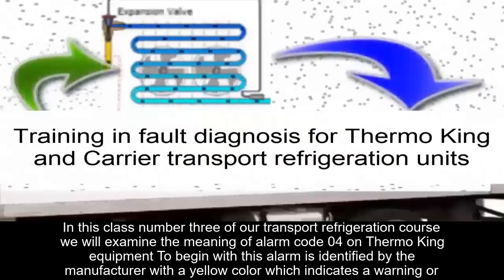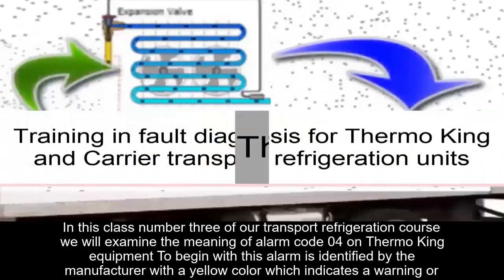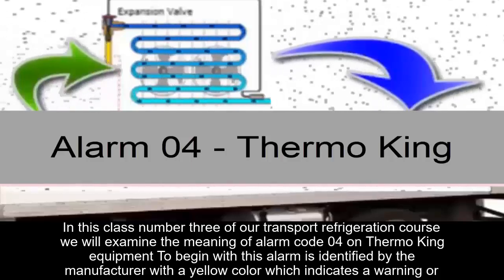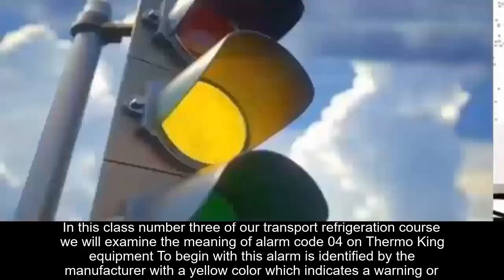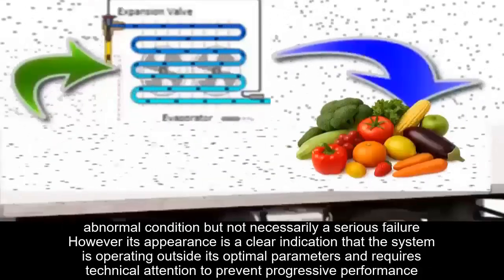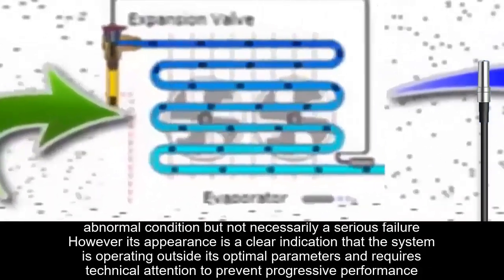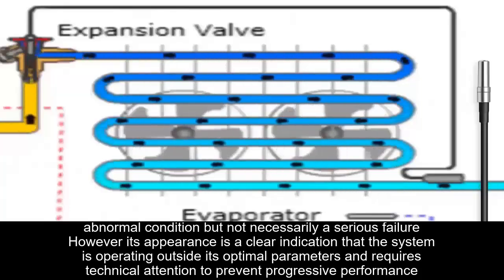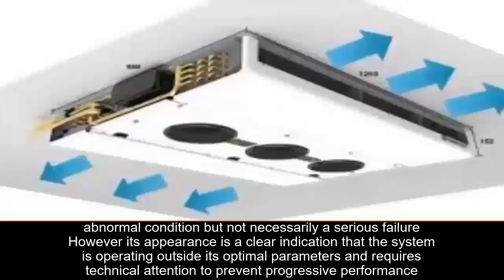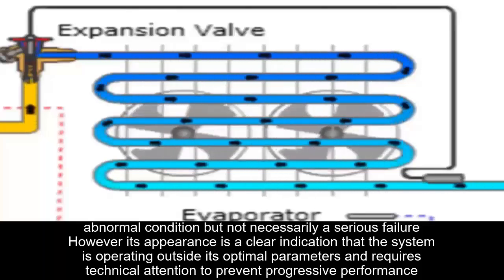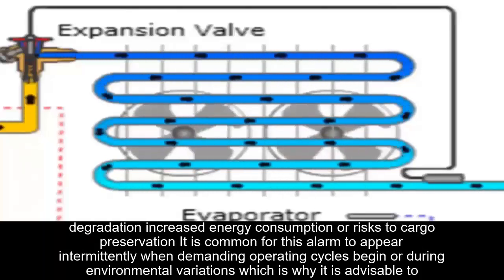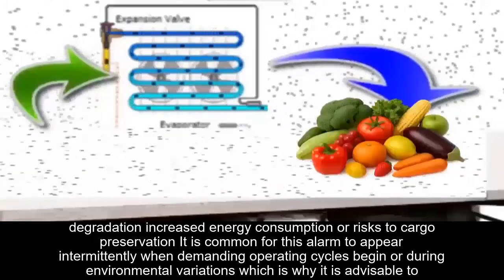In this class number 3 of our Transport Refrigeration course, we will examine the meaning of Alarm Code 04 on Thermo King equipment. To begin with, this alarm is identified by the manufacturer with a yellow color, which indicates a warning or abnormal condition, but not necessarily a serious failure. However, its appearance is a clear indication that the system is operating outside its optimal parameters and requires technical attention to prevent progressive performance degradation, increased energy consumption, or risks to cargo preservation.